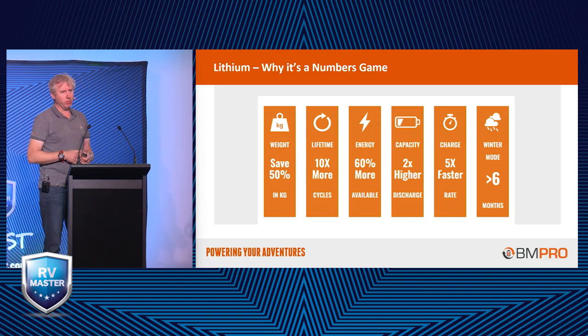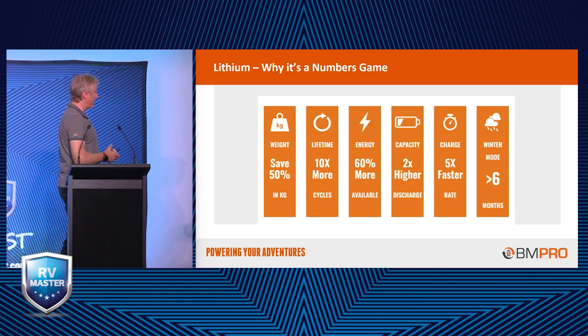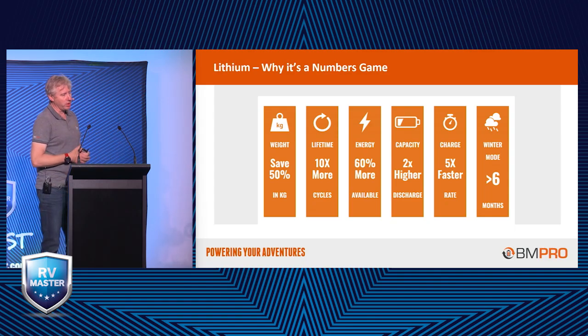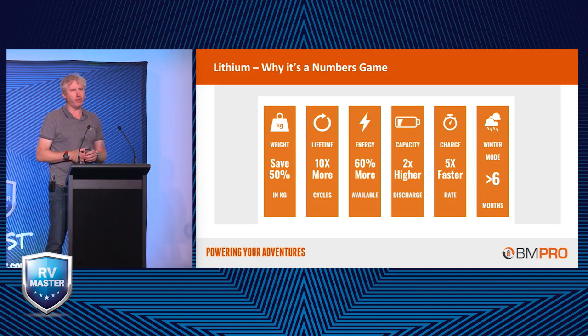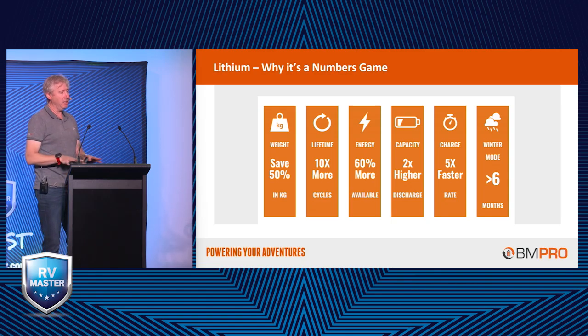The summary is it's actually a really simple numbers game, and I'll go through each in more detail in a minute. From a weight perspective, it's half the weight of a standard lead acid battery, which are big bricks at 27-28 kilos. Lifetime is 10 times more cycles - you'll get a lot more cycles out of a lithium battery than a lead acid battery. Energy, 60% more is available. A lead acid battery you'd normally only charge down to about a 50% depth of discharge, but with lithium you can easily discharge it to 80 or 90% used and leave it at 10 or 20%, no problem. Its capacity can discharge twice as fast.